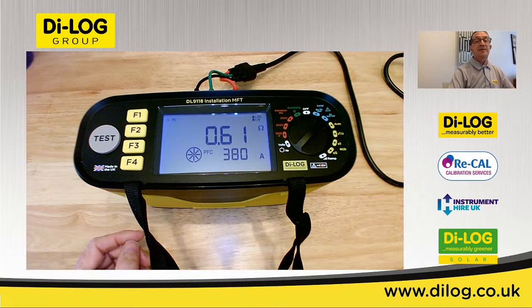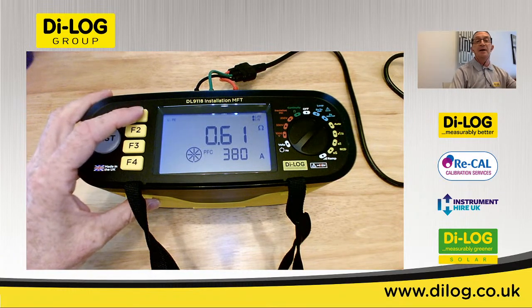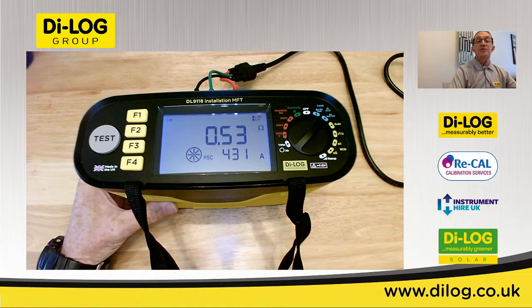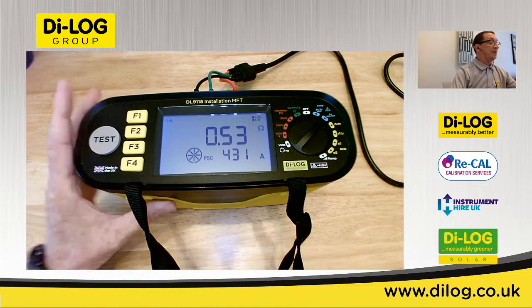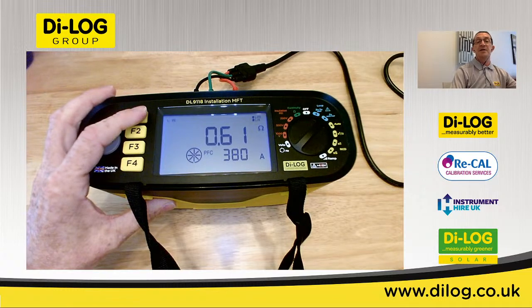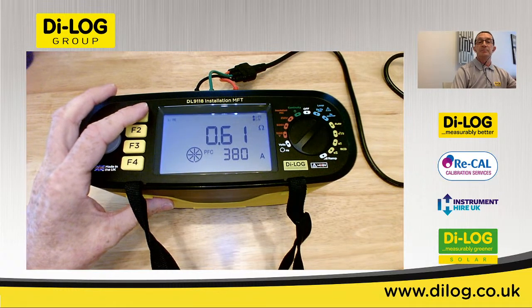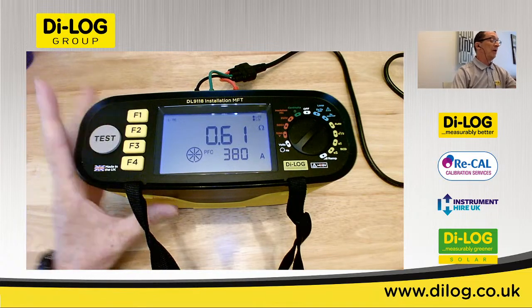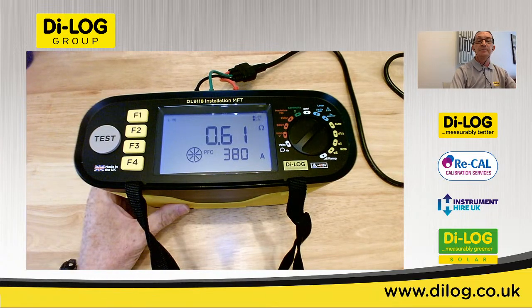Once the test is complete, I can switch between live earth or live neutral, and both PSC and PFC are displayed in one particular test, making testing a little bit quicker and a lot more convenient.